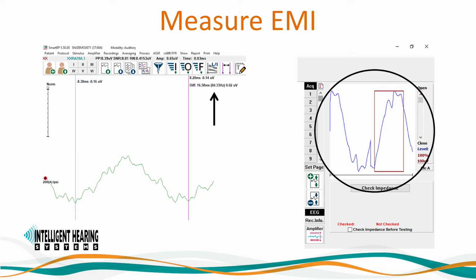While you are trying to identify the sources of the interference from the incoming EEG display, you can also acquire a one-sweep average with filters wide open. For example, say you set your high-pass filter to 1 Hz or 0.1 Hz, while your low-pass filter is set to 3000 Hz or 5000 Hz. Whatever the available bandpass value will depend on the device platform being used. And then set your amplifier gain and artifact rejection. Adjust it so as to accept large signals. For this type of evaluation and analysis, open the artifact rejection to 100%.